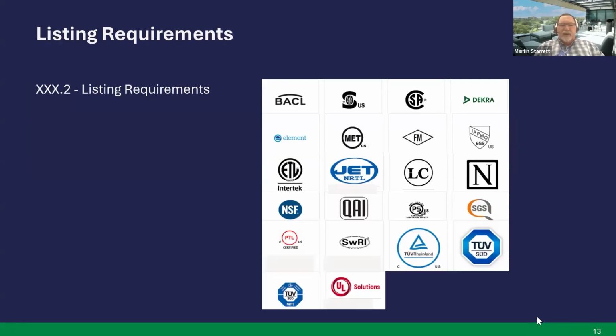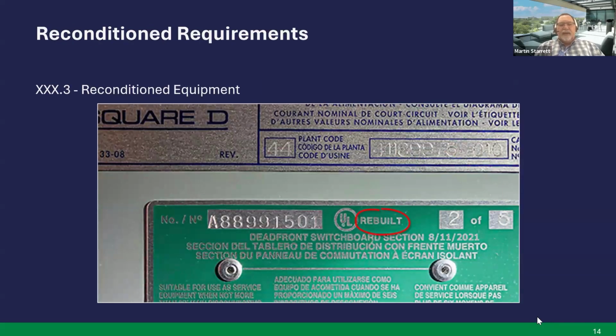So those of you that are pretty familiar with the National Electric Code, dot 2 in prior editions was usually where we found the definitions contained in that particular article, but now all those definitions have been moved to Article 100. They're now using the dot 2 in a lot of the articles as the listing requirements. So whenever you go to a specific article, you look at the dot 2, that's where you're going to see some new listing requirements and then some current ones as well. Next slide. Similar with dot 3, across the code will have your reconditioned equipment, if it's allowed, if it's not allowed. Some of them are still left open. They haven't had anything added to them yet. Next slide.